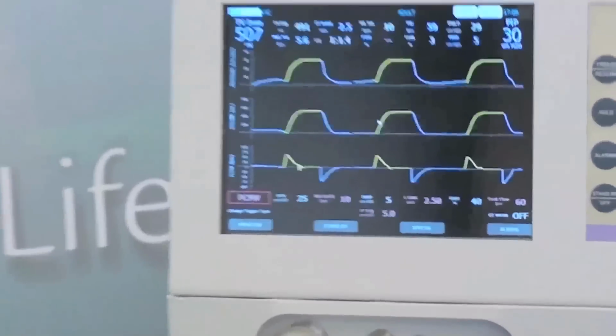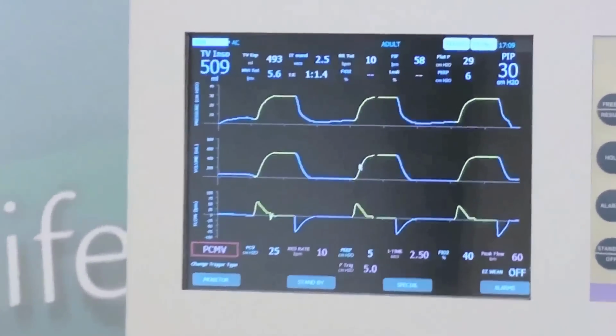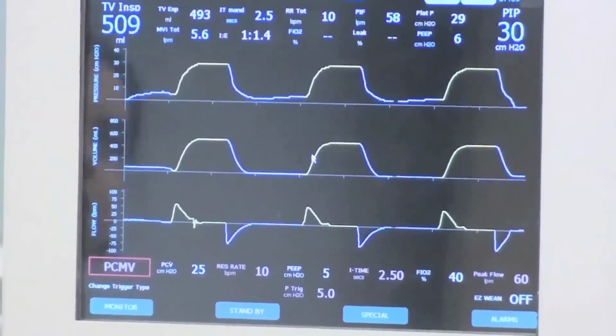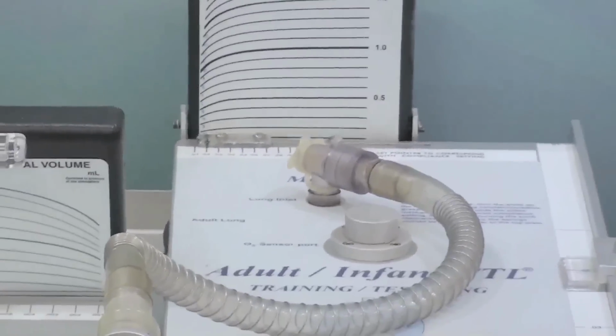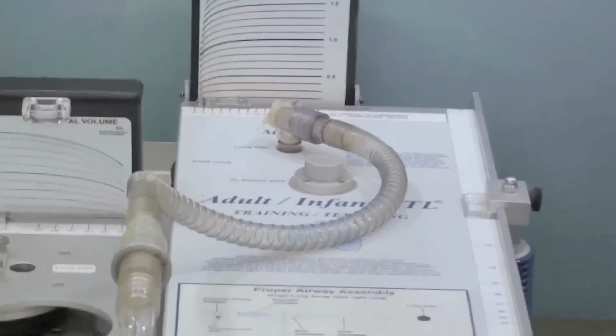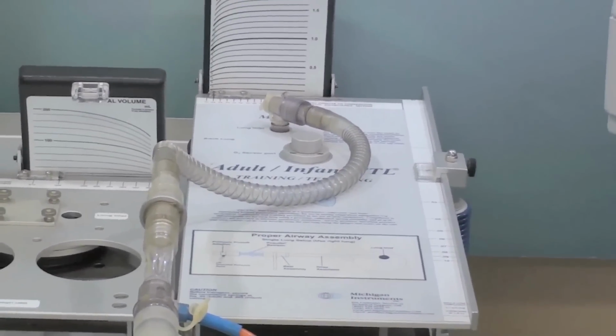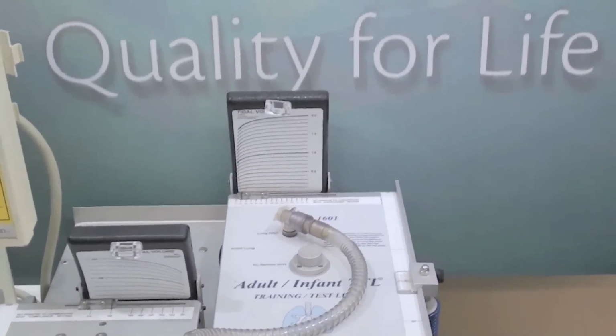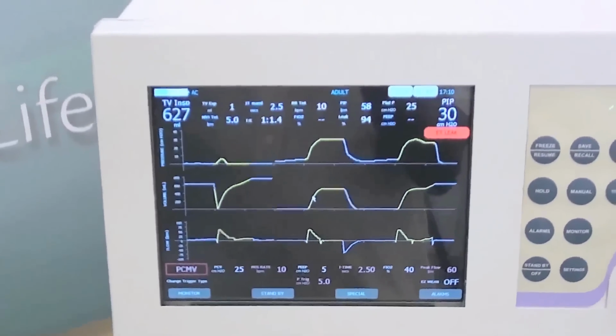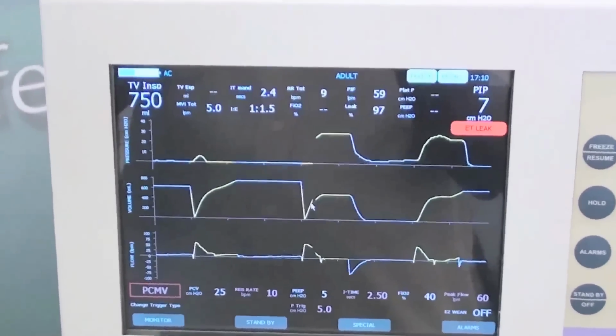We will now observe the effect of an ET side leak on the monitored data when the ventilator uses a patient proximal sensor. The readings of inspiratory and expiratory tidal volumes do not show the presence of a leak. Now, when we introduce a disconnection on the ET side, we observe that there is no rise and fall of the lung. This is expected. There is gas flow towards the ET tube, but due to disconnection, it does not travel to the lungs. We would expect to see an inspiratory tidal volume and little or no exhale tidal volume.